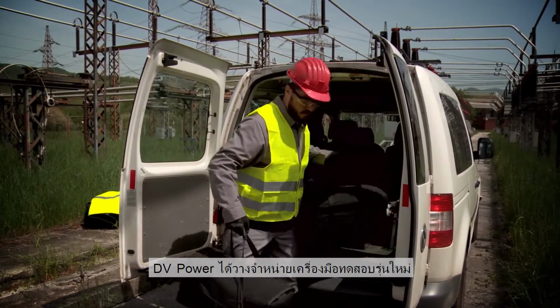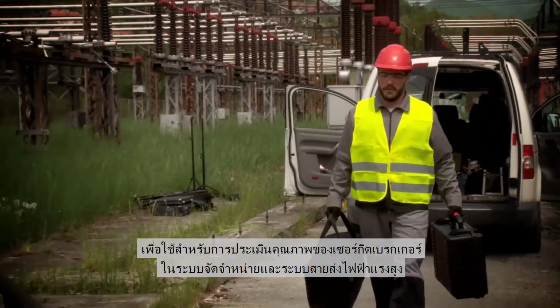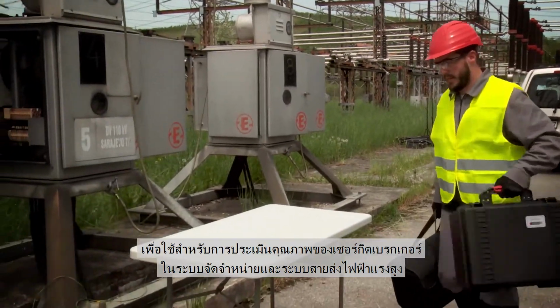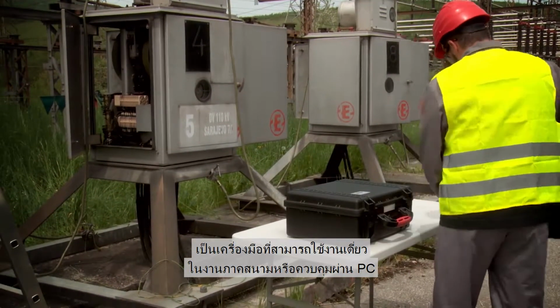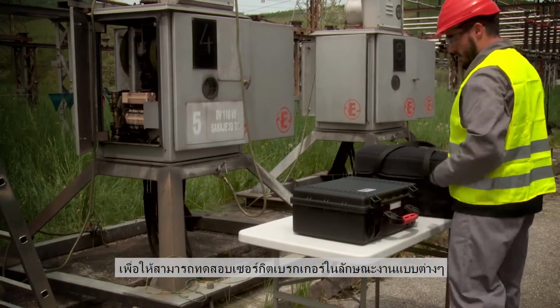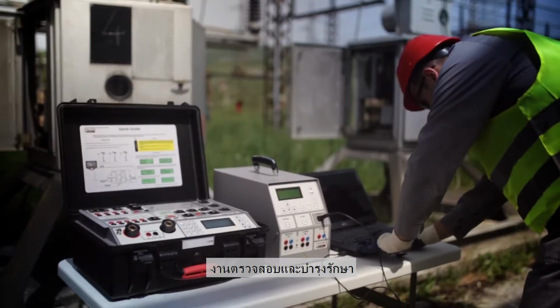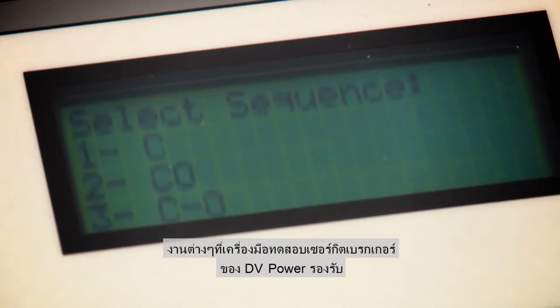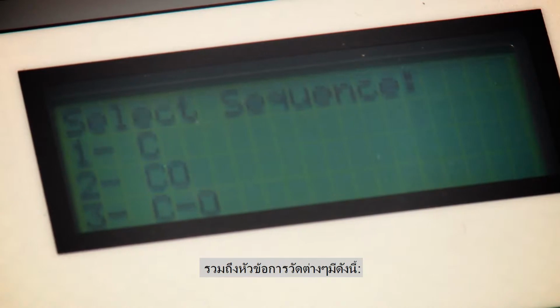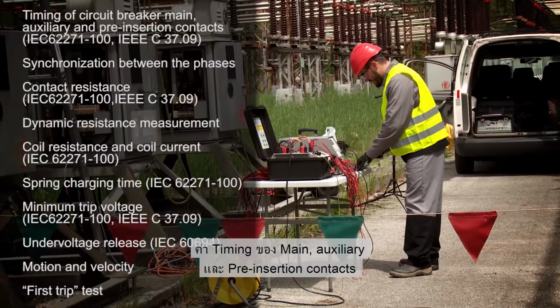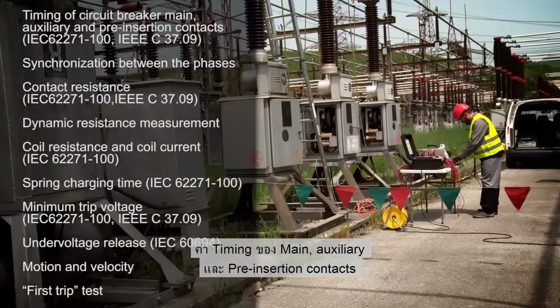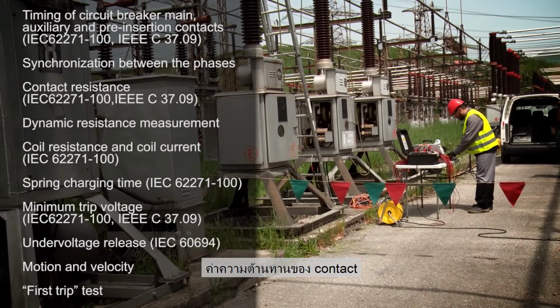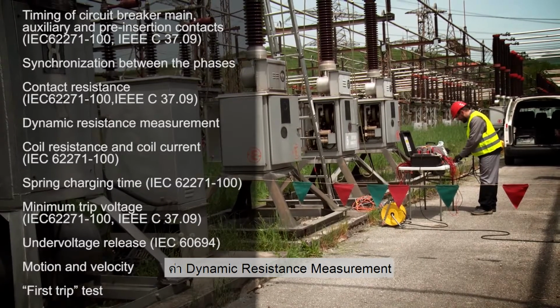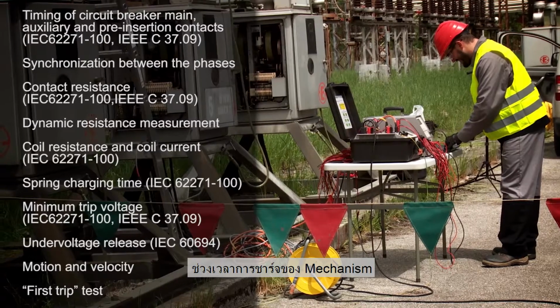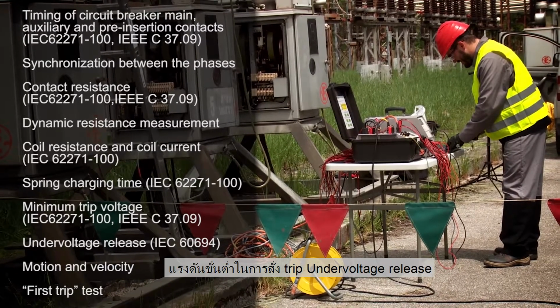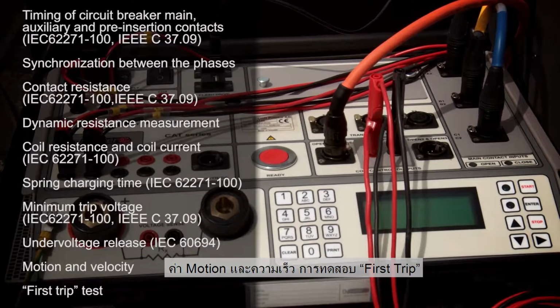DV Power has released a new generation of test equipment for condition assessment of distribution and transmission high voltage circuit breakers. Field portable instruments with standalone or PC controlled functionality allow performing various tests during circuit breaker manufacturing, commissioning and maintenance stages. Applications supported by DV Power circuit breaker test equipment include measurements of timing of circuit breaker main, auxiliary and pre-insertion contacts, synchronization between the phases, contact resistance, dynamic resistance measurement, coil resistance and coil current, mechanism charging time, minimum trip voltage, under voltage release, motion and velocity, first trip test.